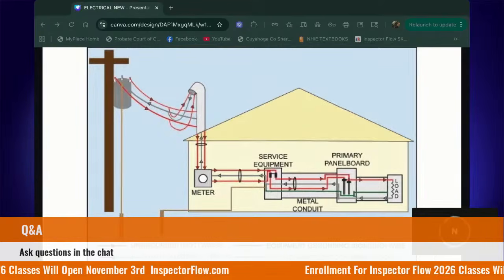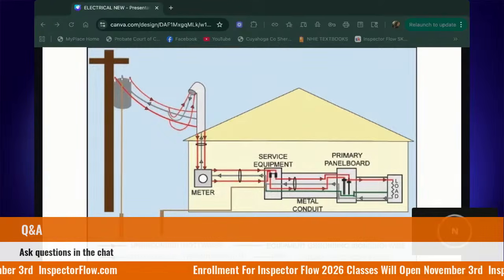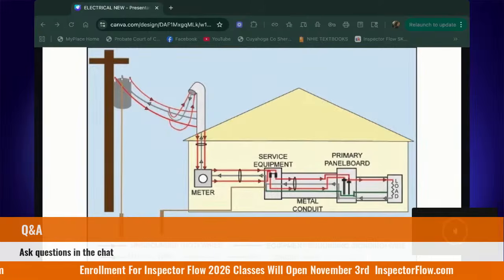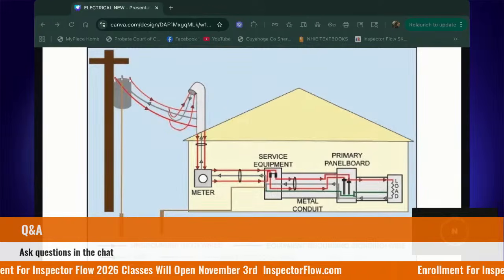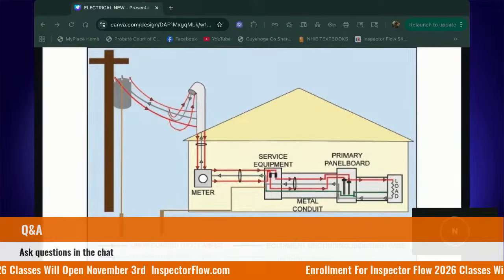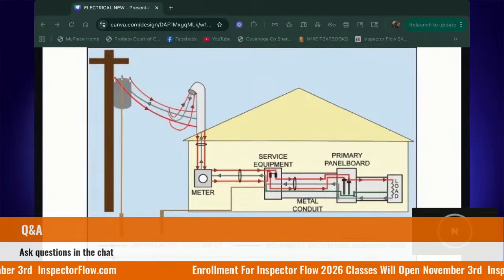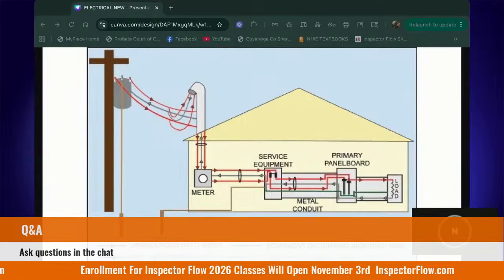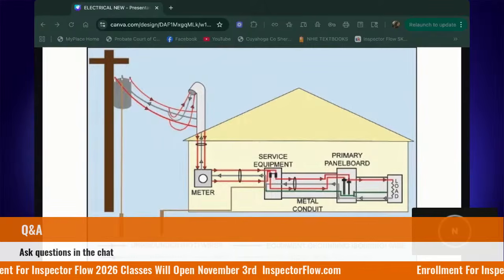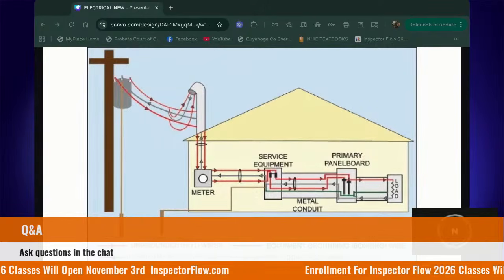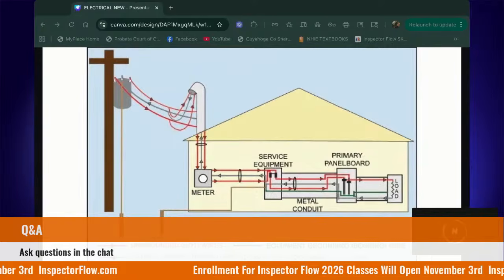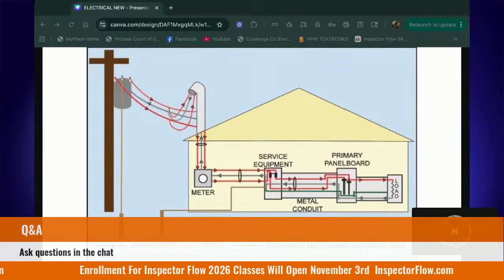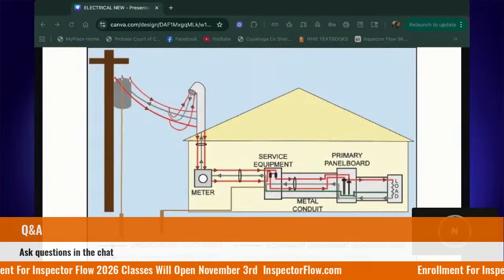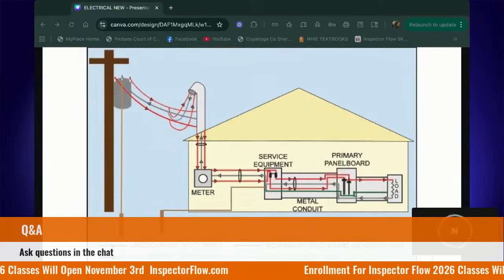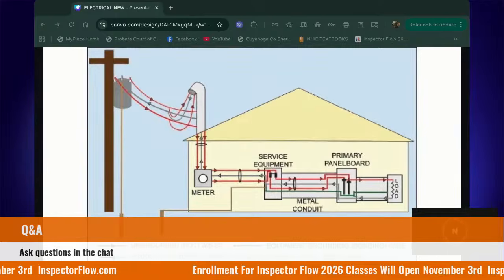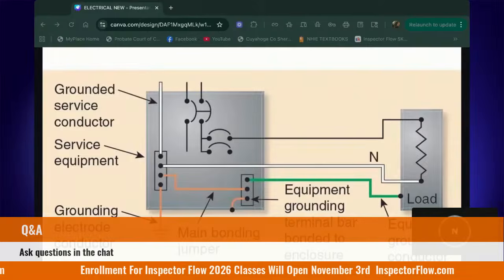Wouldn't that also be copper? What do you mean copper? Because it's grounded. Yeah, it would be copper, but can I find the GEC there? Yes, because they'll be thicker than the other wires. That's what was on the diagram, wasn't it? It would be thicker. So you're saying yes, I could find the GEC on a neutral grounding bus bar. Yes. And that is because why? Because they're bonded. Yes, because the neutrals and grounds are bonded at the main panel. That's correct.